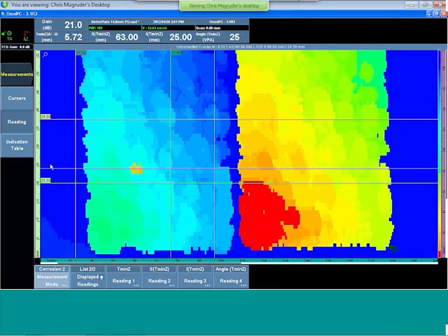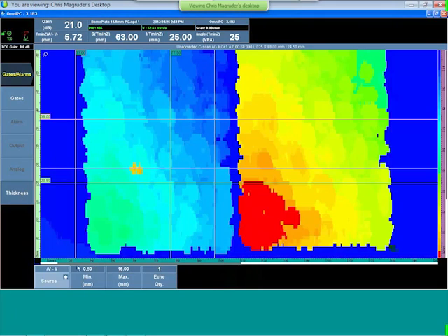Within this box we call the zone, the lowest reading that occurred in the zone was 5.72. That number cannot be smaller than the thickness that I determined here. Once I find the minimum thickness, I can eliminate zeros or false erroneous readings from my statistics by making the adjustment here under the gate minimum. And I could also change this logic.